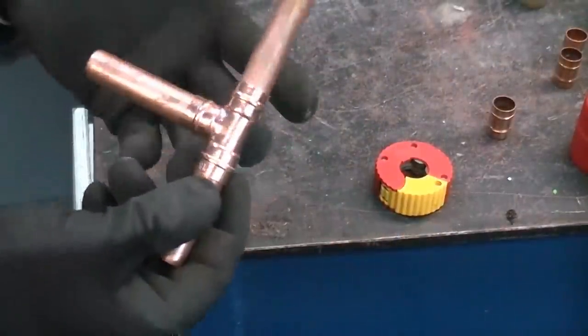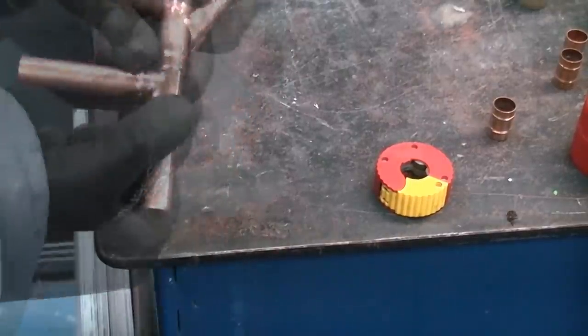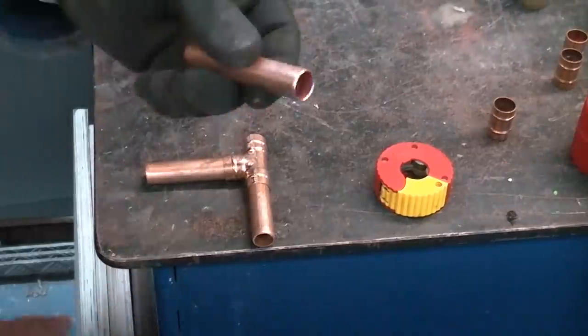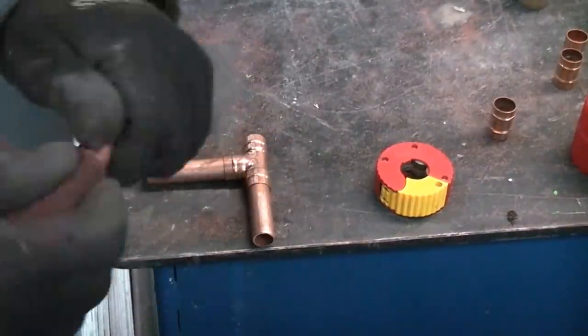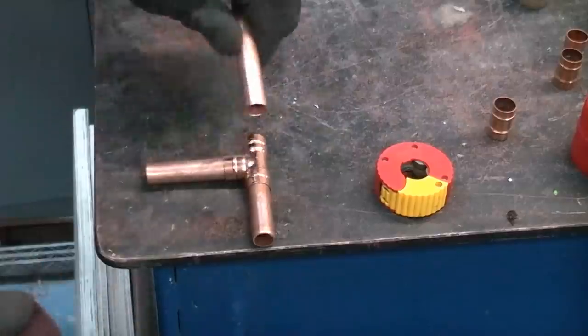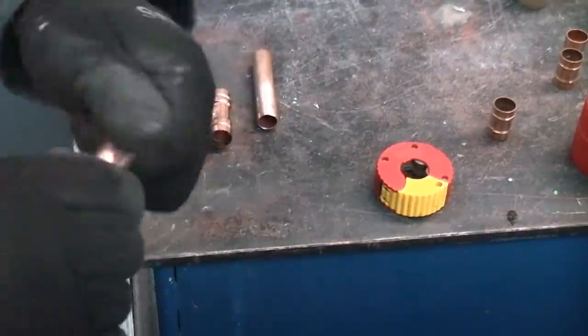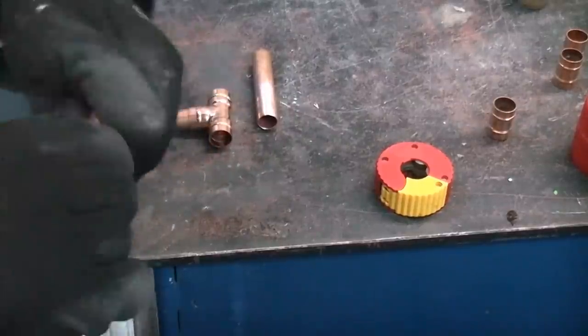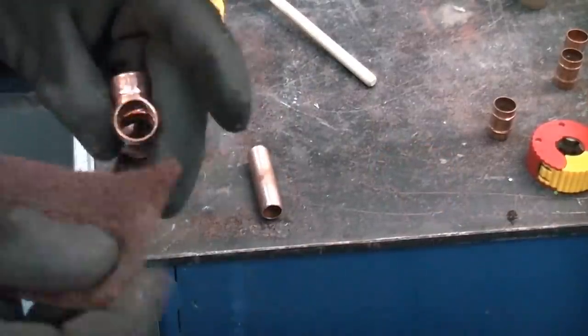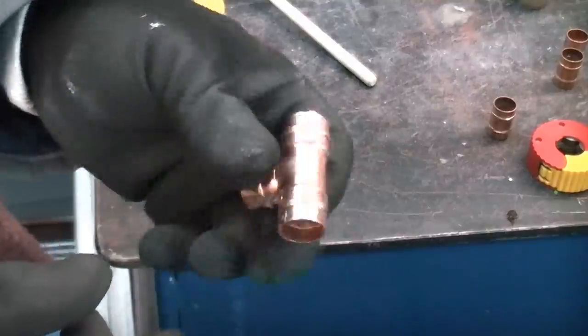When you fit this piece you can actually do all the soldering in one go or you can solder the T-piece first which will make it a little bit easier. In this example I'm just going to solder this part first. Just like I did before, I'm going to clean all of the copper pipe up using the Scotch-Brite pad and also clean the other ends up as well because they're going to be soldered shortly. It's also a good idea if you have an old fitting to cut a piece of Scotch-Brite pad and just clean the inside of the fitting. This one is actually brand new so there's no need to do that.